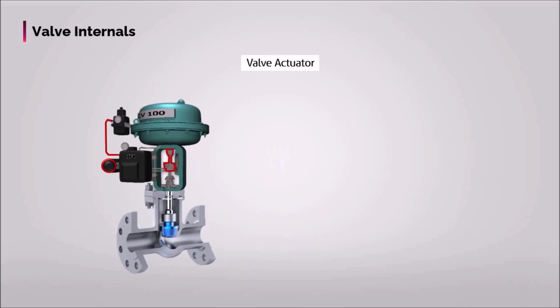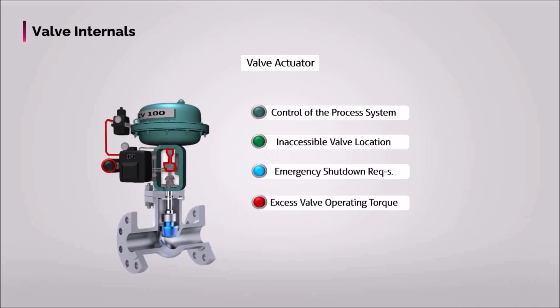The decision for actuating a valve will be made due to one or more of the following reasons: control of process system, inaccessibility or remote valve location, emergency shutdown or fail-safe requirements, excessive valve operating torque and safety.